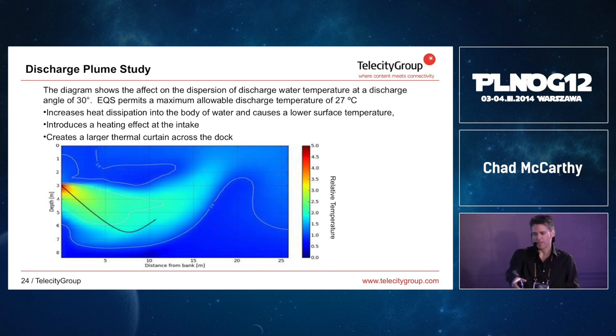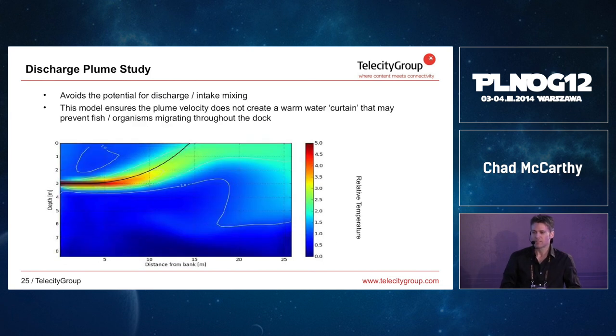So that becomes difficult because we have this mixing effect. We would effectively be drawing in warmer water because we're drawing warm water close to the discharge. So we found that if we discharge at high level, at a 0 degree angle, then the water rises on its own to the surface, increases the heat exchange to atmosphere, and at the depth of 6 meters, that's where we have our connection for the replacement water, which means we no longer have mixing, and we can take the lowest possible water temperature from the dock into our data center.